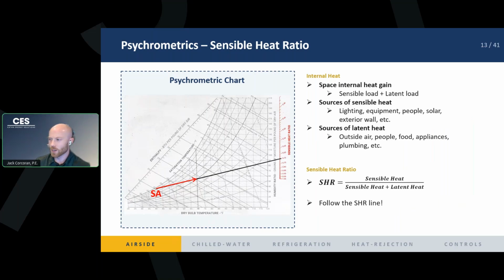And so you can imagine the same thing can be said if we're dumping our supply air into the space, right? If we dump the supply air, which is our leaving air temperature of our unit, into the space at 40 degrees Fahrenheit, and you let it slowly drift up along this red arrow, that is going to allow you to hit that 70-degree space and 50% relative humidity, right?